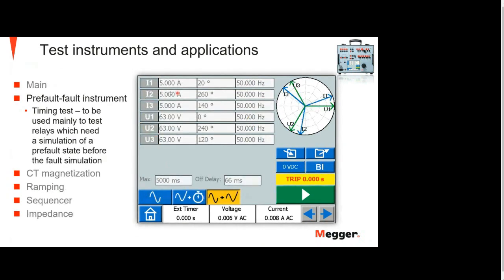Here is the pre-fault instrument. It looks like this. Here you set the pre-fault values, so you push there. And then you set the fault values here, and how long the time is, for example. And then you're ready to go. You push here, and when you would like to play this, you push on the play button. So that's a pre-fault simulation. And you will have the tripping time, for example, here, if you're measuring the time.